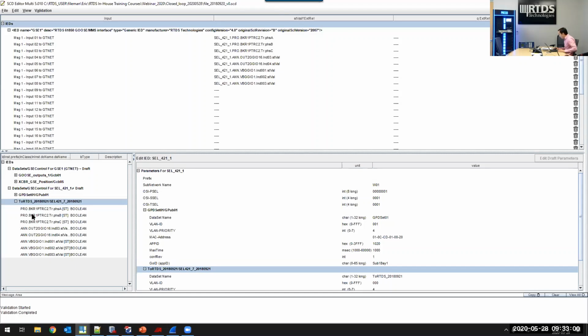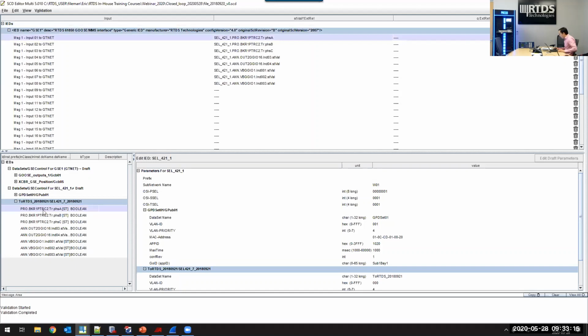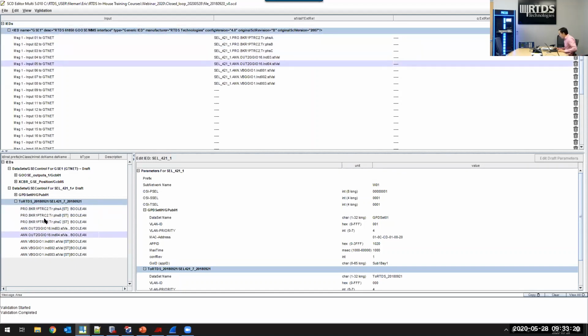As we discussed earlier, we expect the relay to send the trip and reclose signals. In this demo, the relay was configured to send a GOOSE message with a dataset containing this required information. Here, the Boolean attribute 1 to 5 are representing A phase trip, B phase trip, C phase trip, reclose, and the permissive transfer trip, respectively. Again, ignore the rest.